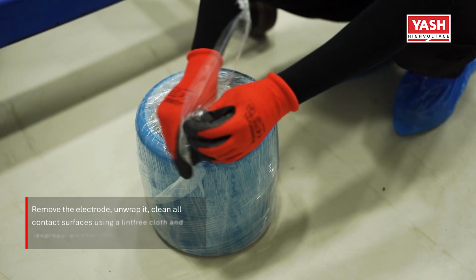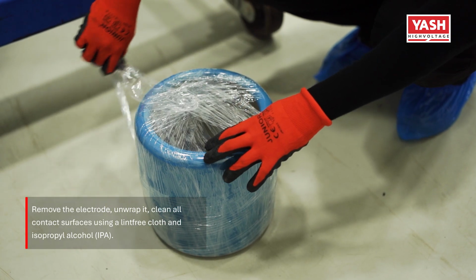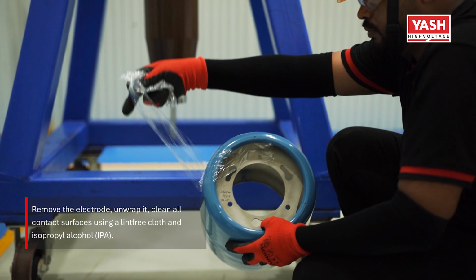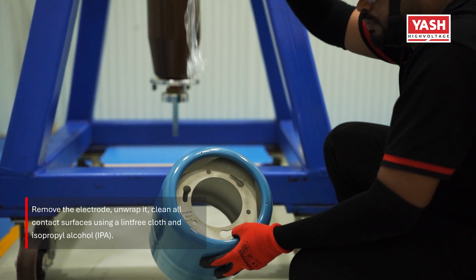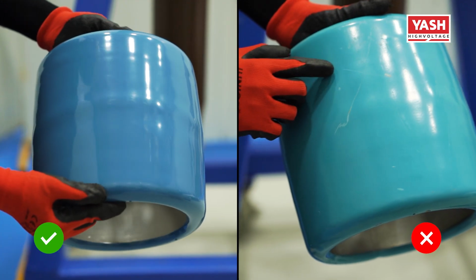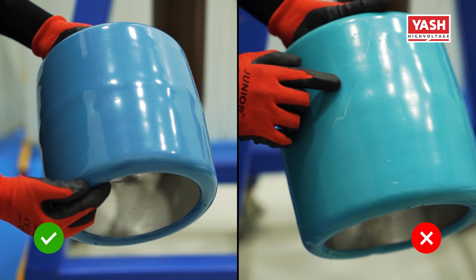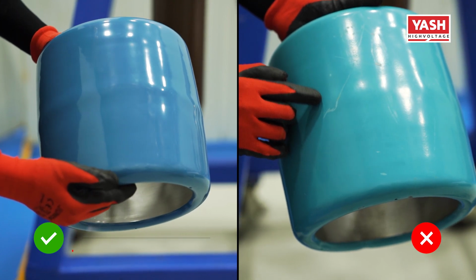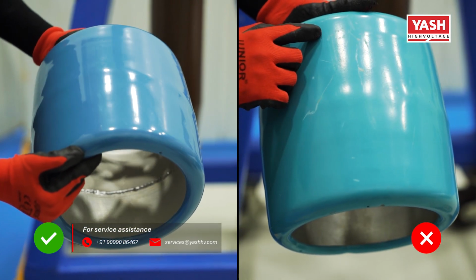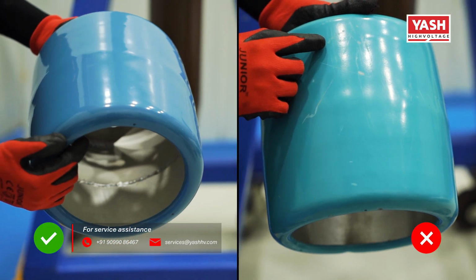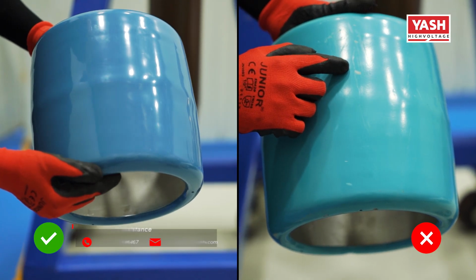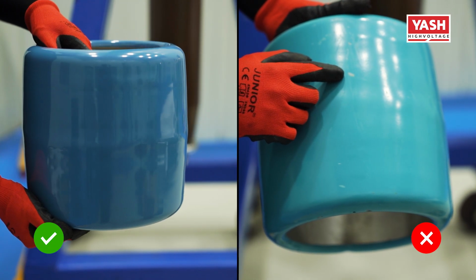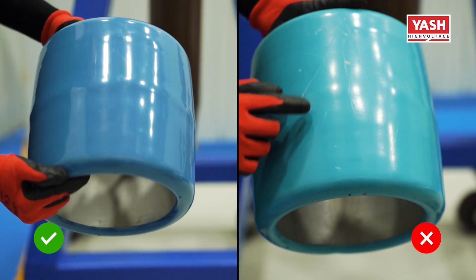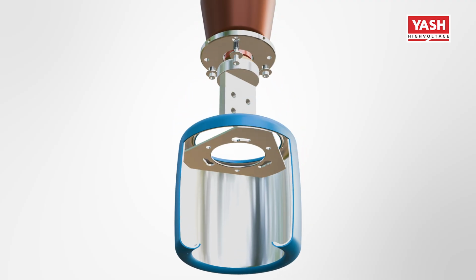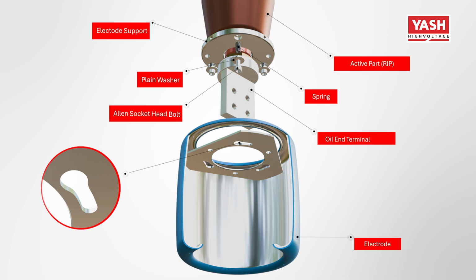Remove the electrode, unwrap it, clean all contact surfaces using a lint-free cloth and isopropyl alcohol. After unwrapping, inspect the electrode for any damage or corrosion. If found, immediately contact the Yash team, as defects on the electrode or its coating may cause failure or flashover during service or testing. To ensure proper handling of the bayonet electrode, let's start by understanding its key components and parts.